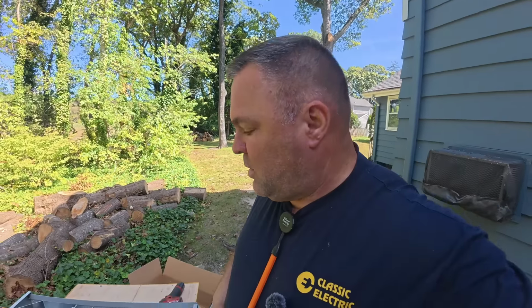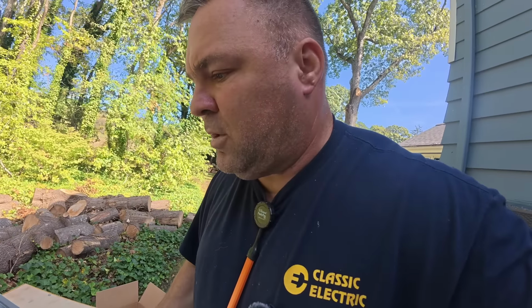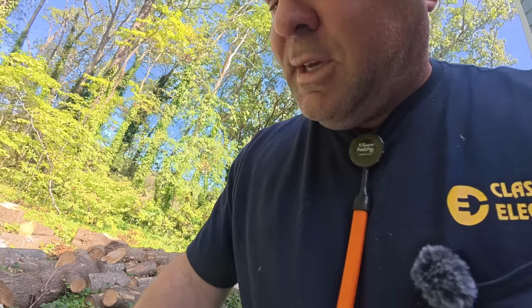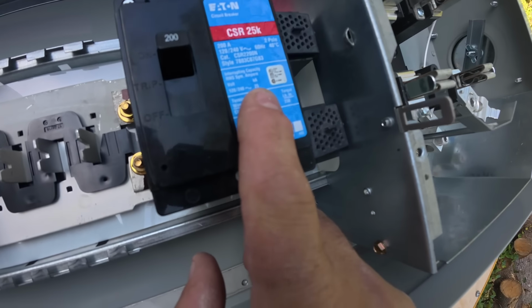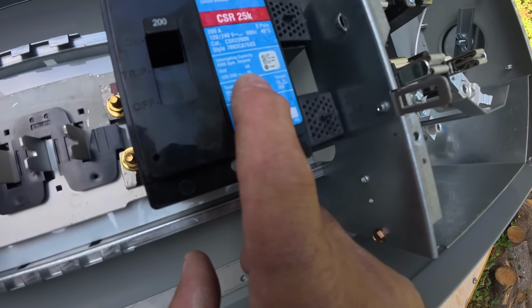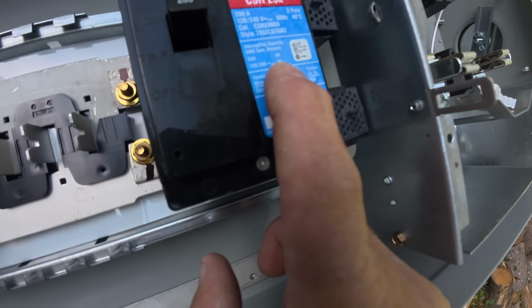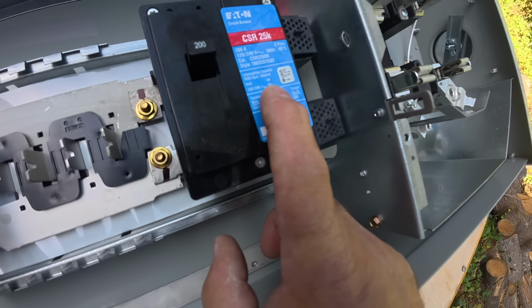Okay, so some of you might want to know what these numbers are on the circuit breaker other than where it says 200 amps. The number you'll see here is the interrupting capacity number, which is 25,000 amps. Okay, 25 kA, so that's kiloamps, 25,000 amps. What that means is that rating on this main breaker right here needs to be able to be more than the available interrupt current coming from the utility company.